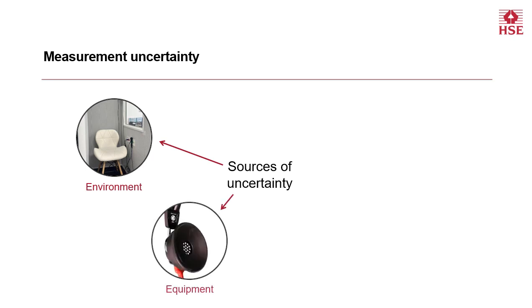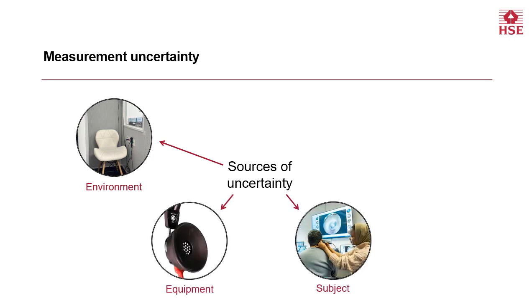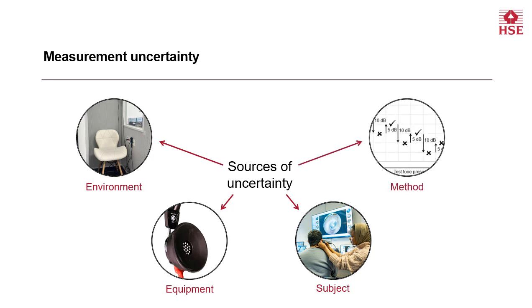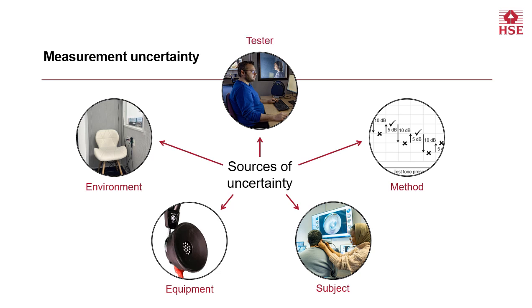Psychophysical measurements, like the measurement of hearing threshold, are subject to measurement uncertainty. Some of this is random variation that cannot be controlled, but other sources of uncertainty are within your control. These sources include the measurement environment, the equipment, the subject, and by subject I mean the employee whose hearing you are testing, the method that you use for making the measurements, and you, the tester. In order to detect a real change in an individual's thresholds, it is crucial that you minimize the uncertainty where you can through good quality measurements. In this webinar, we shall consider each of these sources in turn.